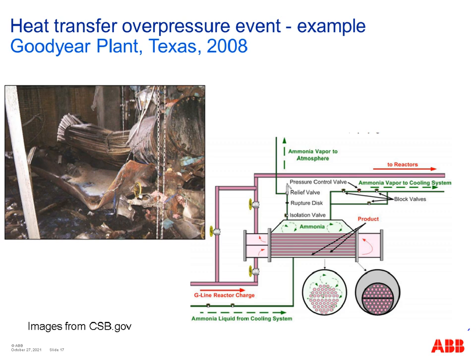So ammonia liquid comes into the heat exchanger as a liquid, and with the energy it removes from the process stream, it's then heated up, so it leaves the heat exchanger as a vapor, and normally it passes on to the cooling system via the pressure control valve. There's also another outlet line for the ammonia vapor, and that's to a rupture disc and relief valve.